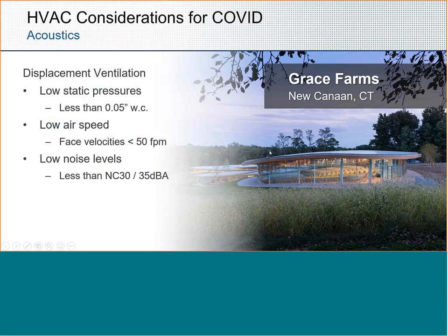Lower noise: a lot of times we see it applied in concert halls and auditoriums for these reasons. Again, that low static pressure and low airspeed used to supply these diffusers results in noise levels well below NC30. And there are a lot of selection criteria.